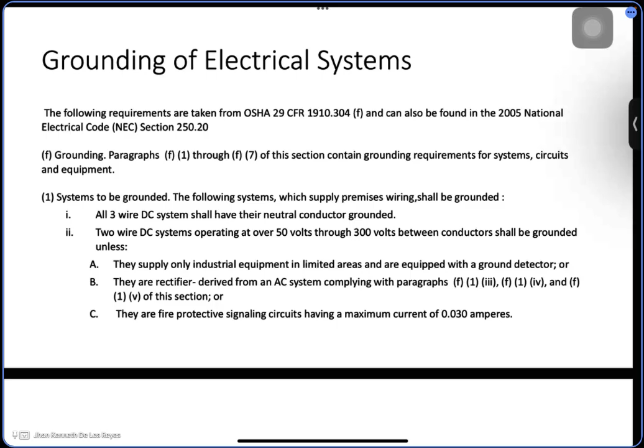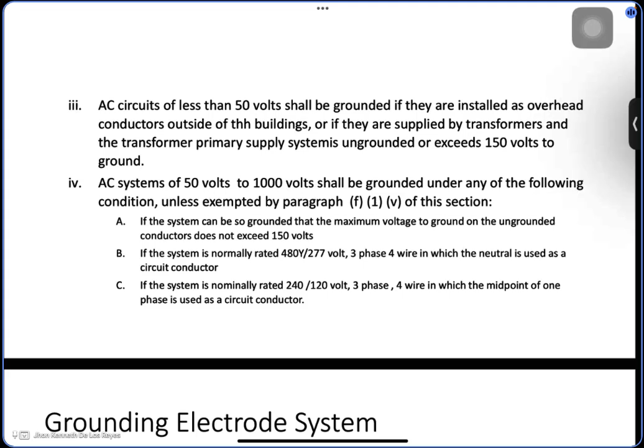Under OSHA, it really identified which AC or DC system requires grounding safety. An AC system must be grounded if the ungrounded conductors do not exceed 150 volts to ground. Also, if the system is 480Y, wye connection, 277 volts, three-phase neutral used, and if the system is 120/240, we have primary and secondary volts, three-phase midpoint is used. We have a configuration that depends heavily on neutral. Grounding is really essential even if it's AC, and an AC system with neutral use or low to ground voltage must be grounded.